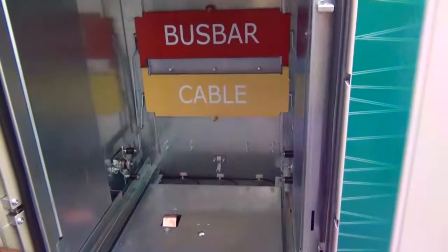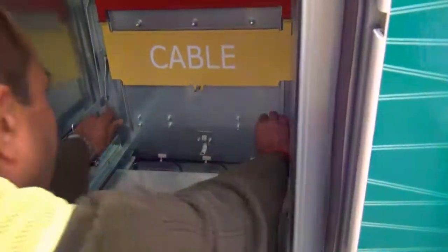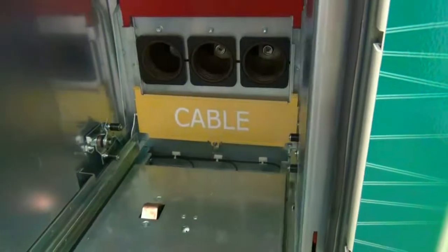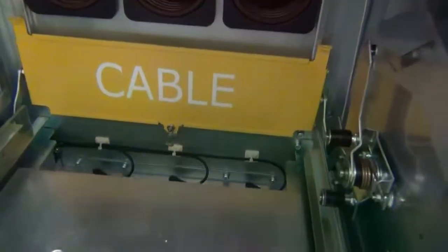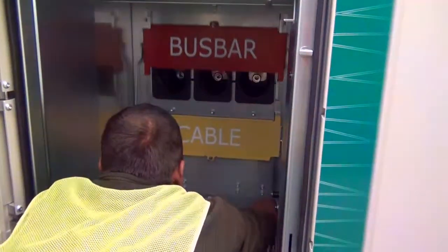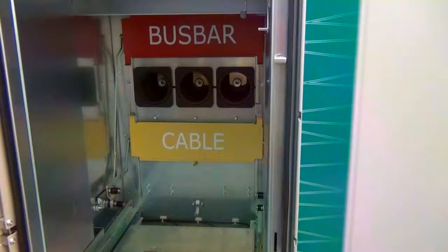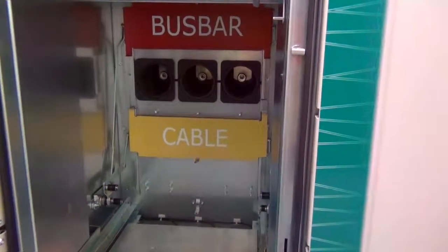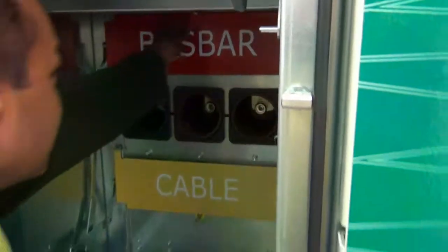Now, if you want to access the cable side, one can do that. One can defeat the interlock. Both the rollers are to be pushed together, and now you can access it. And as you can see, there is an arrangement to padlock the same as well. If you press it once, this will come back again to its original condition. Similar is possible for the bus bar side of the compartment. Similarly, you have a padlocking arrangement, and as soon as you press it out, even that can be defeated.